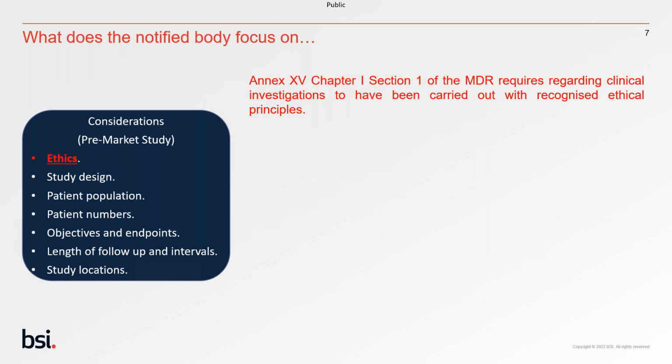So the first one is ethics. Annex XV, Chapter 1, Section 1 of the Medical Device Regulation requires that clinical investigations be carried out in accordance with recognized ethical principles. And those ethical principles and plans need to be clear from the initial study design right through to the publication of the results of your clinical study.